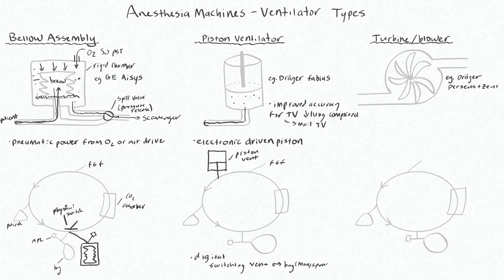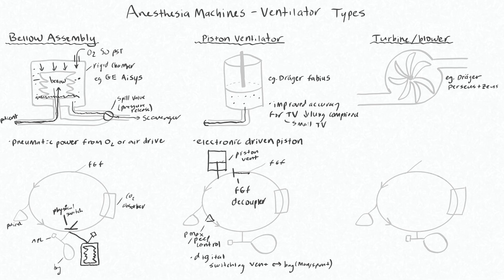Some other components of this circuit are the pressure max and PEEP regulator. There's also a device called the fresh gas flow decoupler, which prevents the fresh gas flow from contributing to the volume delivered to the patient. Since this vent is very accurate at delivering certain tidal volumes, when it's delivering air to the patient, the decoupler prevents the extra flow from fresh gas from adding a little bit more to the tidal volume.